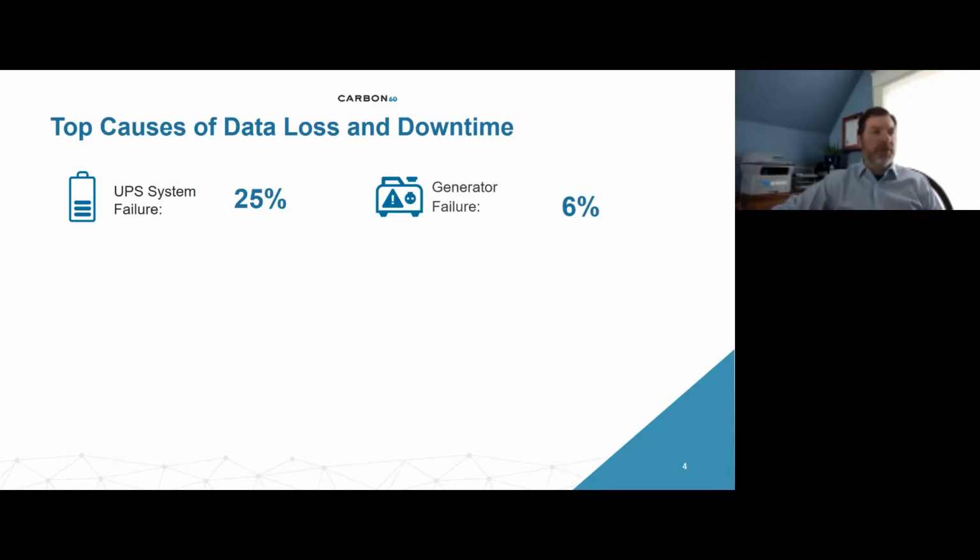I've even seen simple things, as a customer had a new generator, a single generator, and didn't realize that the battery in the generator was not being charged by the generator. They went through a number of tests with it, but when it came time for an actual failure, the generator wouldn't start. And it's pretty hard to do jumper cables on 24-volt systems in that case.